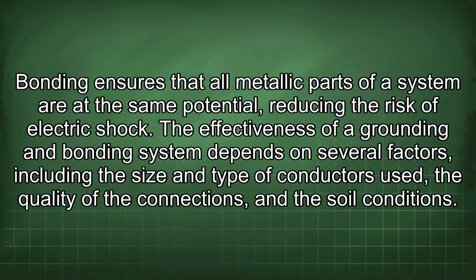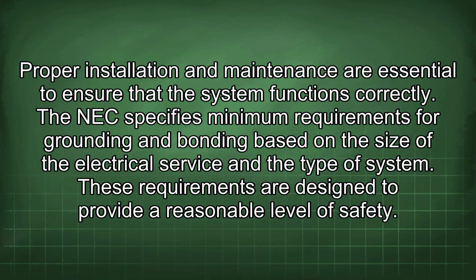The effectiveness of a grounding and bonding system depends on several factors, including the size and type of conductors used, the quality of the connections, and the soil conditions. Proper installation and maintenance are essential to ensure that the system functions correctly. The NEC specifies minimum requirements for grounding and bonding based on the size of the electrical service and the type of system. These requirements are designed to provide a reasonable level of safety.